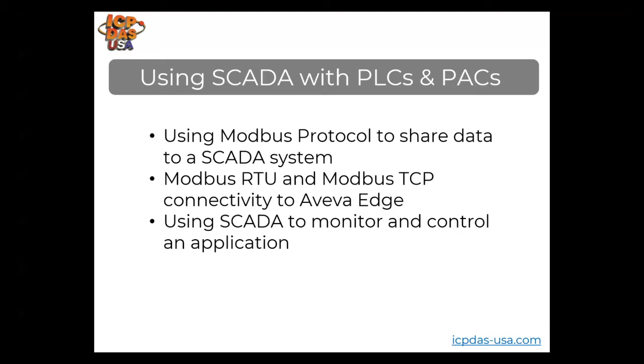For systems with, say, a packaging machine, the packaging machine is controlled by a single PLC, but it's also tied to a production machine for the raw material that goes into the packaging. So you can control and see both systems using communication through a SCADA system like AVEVA Edge or InduSoft.